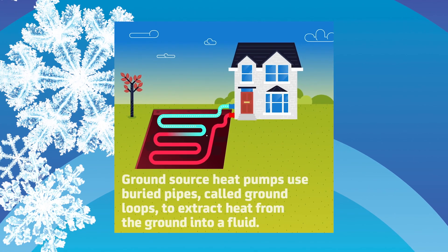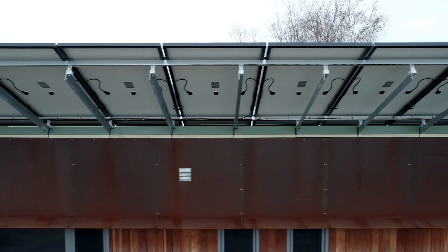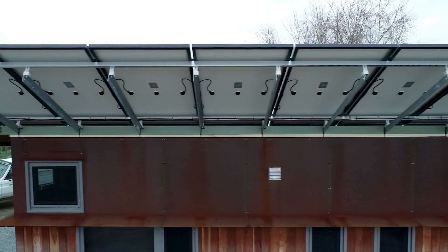The heat pump operates happily in winter because it's sunk underground — it's called a ground-source heat pump. We're lucky in Australia; the air never really gets that cold, and a good heat pump will happily work down to minus 10 degrees C. Do this in Hobart and you can get your 31 kilowatt hours per day down to closer to 11 kilowatt hours, which on an average winter day in Hobart can actually be covered by around 6.6 kilowatts of solar.